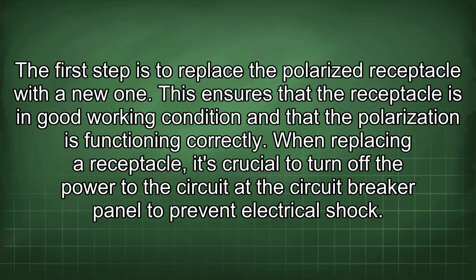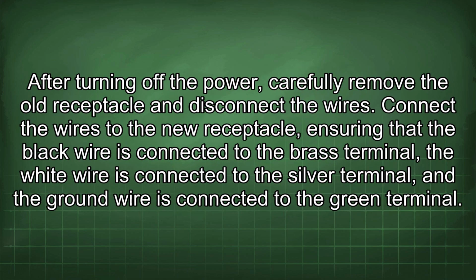The first step is to replace the polarized receptacle with a new one. This ensures that the receptacle is in good working condition and that the polarization is functioning correctly. When replacing a receptacle, it's crucial to turn off the power to the circuit at the circuit breaker panel to prevent electrical shock. After turning off the power, carefully remove the old receptacle and disconnect the wires.